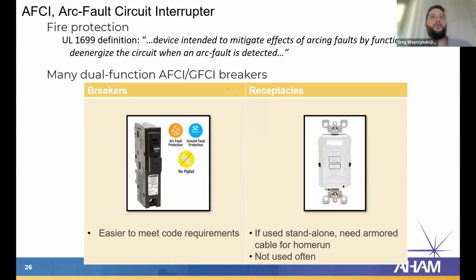AFCIs are arc fault circuit interrupters, and AFCIs are very different from GFCIs. An AFCI's purpose is to prevent electrical fires, not electrical shock. In a lot of cases, you'll see AFCIs implemented in a circuit breaker form. In almost all cases, it's implemented in a circuit breaker form, and you'll see it bundled with a GFCI. So you'll see a single breaker that does AFCI and GFCI protection. There are AFCI receptacles on the market, but they're very rare.